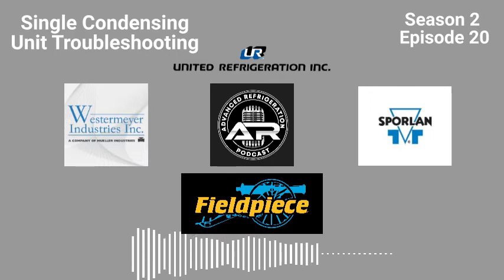I like when pulse valves actually are controlled by EPRs. But the problem is a lot of manufacturers want to not put in an EPR. And we have another store that has a similar issue with the pulse valves, where we have a hard time maintaining. They act like it's a cheap sell. Like, oh, we're going to give you this. It's your liquid line solenoid. It's your defrost valve. It's your temperature control. It's God's gift to control. But like you can't run it.